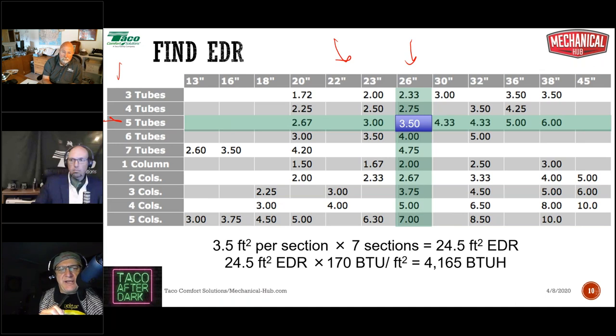In this example, 24.5 square feet worth of EDR times 170 BTUs per square foot means that radiator has a potential output of 4,165 BTUs. So 3.5 square feet per section times seven sections is 24.5 square feet of EDR for that radiator. 24.5 square feet of EDR times 170 BTUs per square foot gives us a potential output of 4,165 BTUs. If we wanted to put that radiator in the room we just did, we're good, because that was only 4,022. We got 4,165. We call it a day.